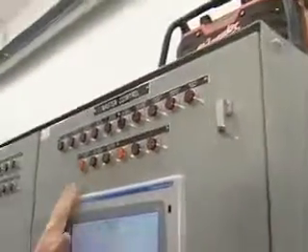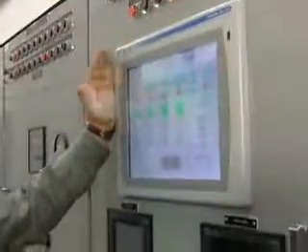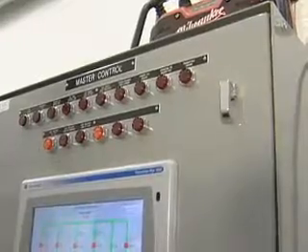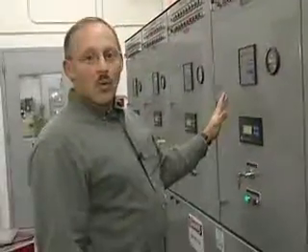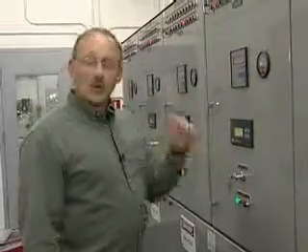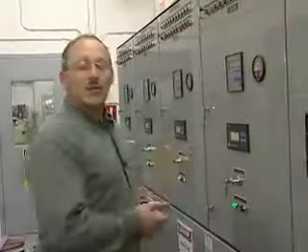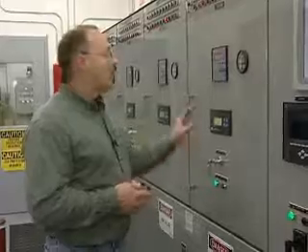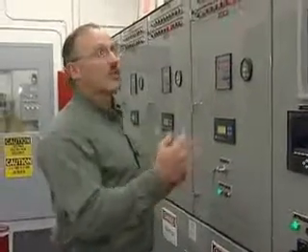From there we go into our PLC — our programmable logical control. Our primary PLC runs the system normally. If there's a failure in that PLC, a red indicator light comes on and our backup PLC takes over. There are two PLCs in this system for redundancy. If both fail, any machine in the auto position will start up, come online, synchronize to the bus, and run in parallel. At that point you're in manual mode and the operator must come in, determine what's going on, and manually shut down generators to diagnose the PLC problem.